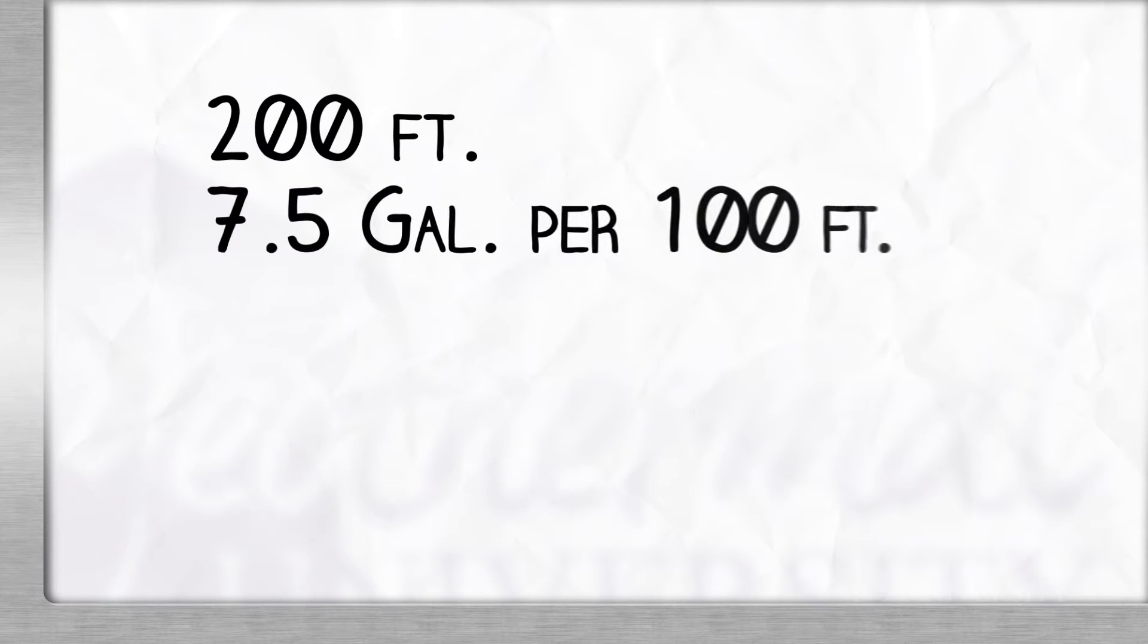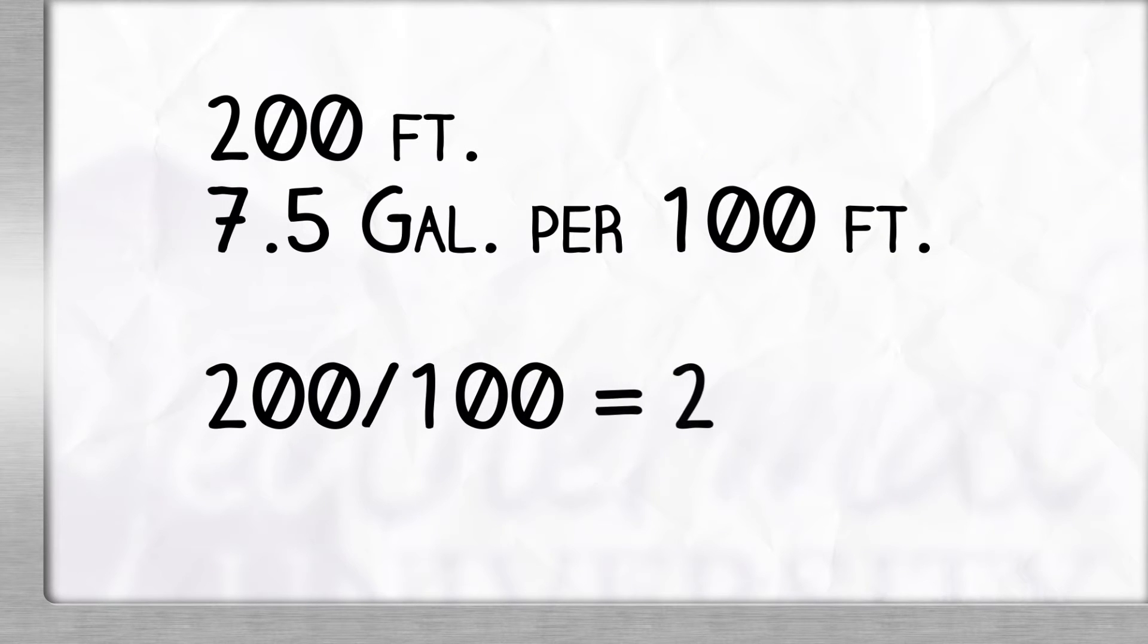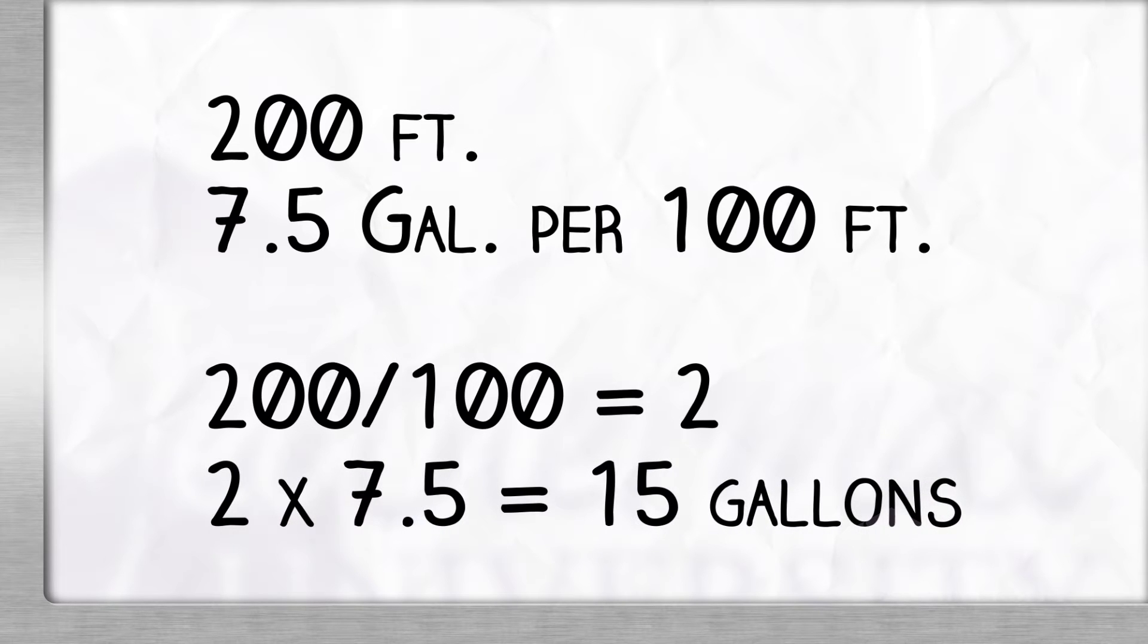So, our calculations are 200 feet of inch and a quarter pipe, 7.5 gallons per 100 feet. 200 feet divided by 100 equals 2. 2 times 7.5 gallons is equal to 15 gallons.